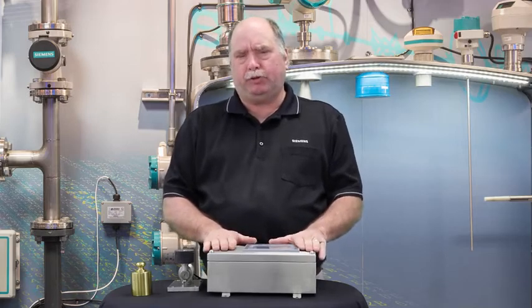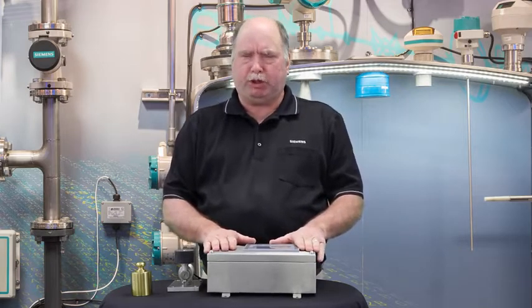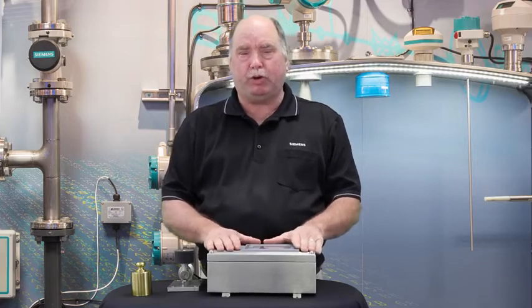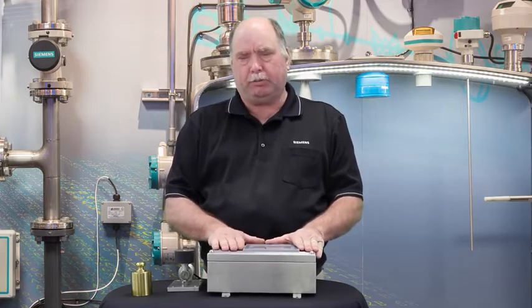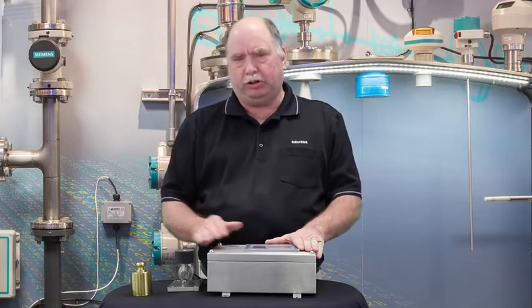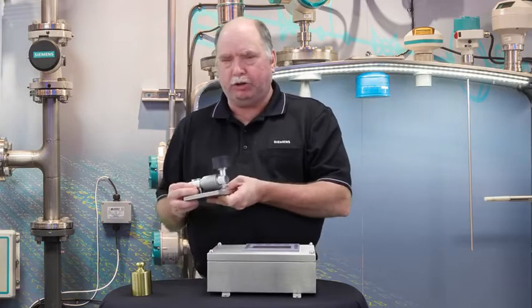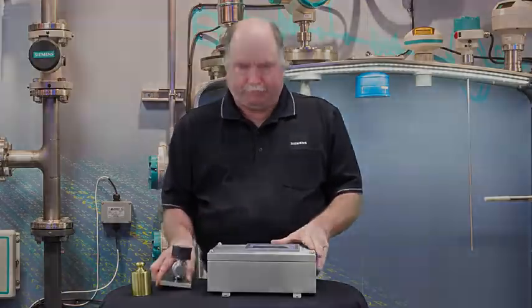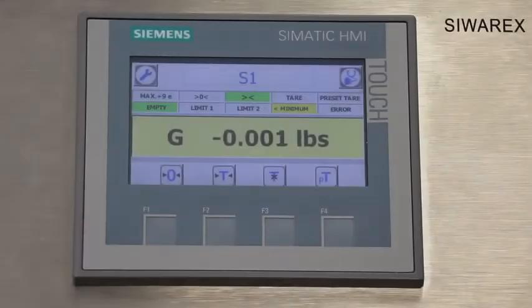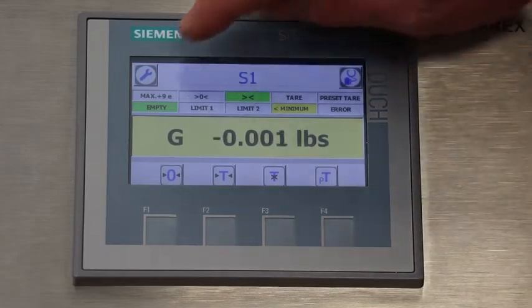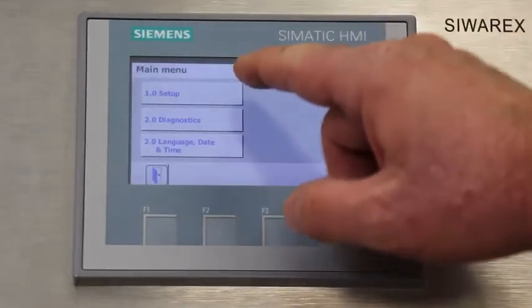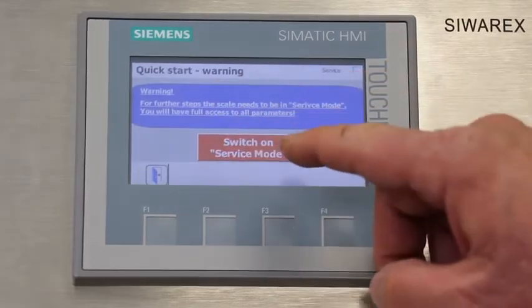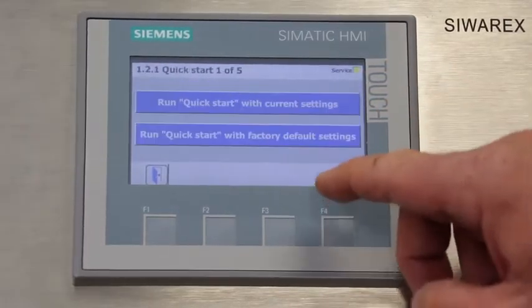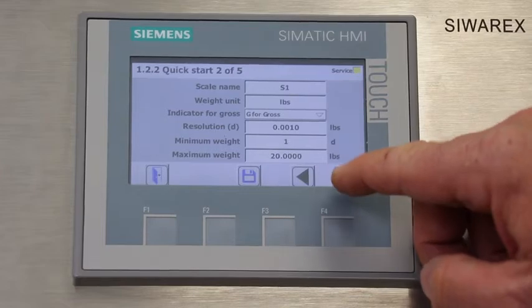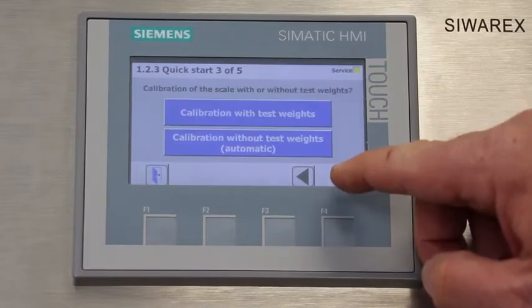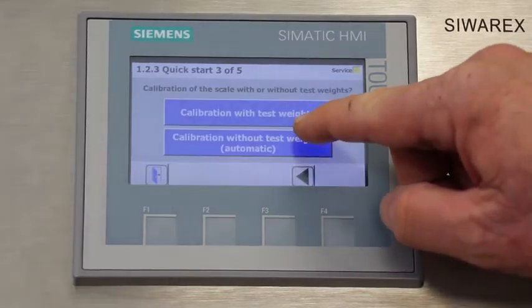Now let's say for some reason you can't use a calibration weight because maybe the scale is too large or you just don't have a weight available to you. Well, you can also set up the WT231 using the information found on the load cell. Now we'll step through that. So now I'll demonstrate how to calibrate the scale if you don't have a calibration weight available. Again, we'll go back to the screen that asks what type of calibration you would like to perform. And this time we'll select an automatic calibration.